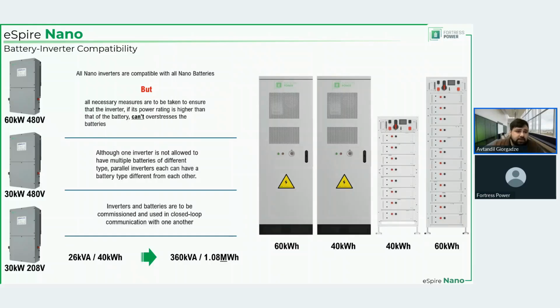Before we dive deeper, this is another important thing. What you were seeing on all these little diagrams were the outdoor batteries. We also have indoor racks. All batteries and all inverters are compatible with one another. So a 40 kilowatt hour battery can work with a 30 kilowatt inverter or a 60 kilowatt inverter, although it must always be ensured and guaranteed that the inverter cannot overcharge the battery.